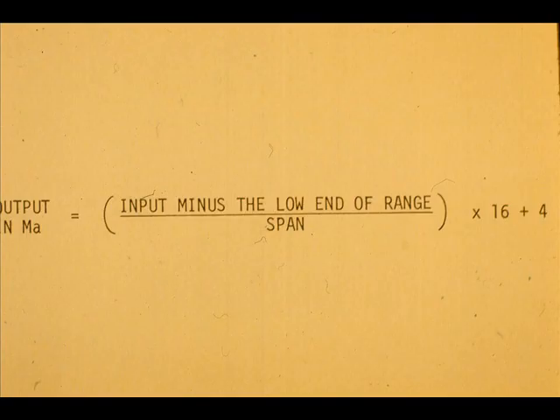These four different transmitter ranges have the same 200 PSIG span. Note that the 0, 25, 50, 75, and 100% of span inputs have the same milliamp output for each range.